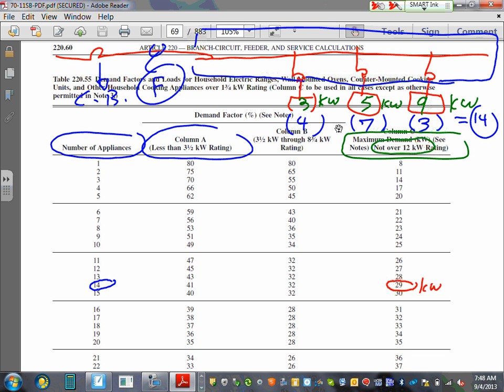You're going to say, okay, does column A apply to any one of them? Can you guys look at that? I have 3 kW. Is 3 kW under column A? Right? It says less than 3.5 kW. So all these ranges, column A applies to them. Can I have thumbs up? Yeah, we understand that, chat? Okay. Then you go to 5 kW. Is 5 kW under column B? Yep. So column B applies to them. How about the 9 kW? The 9 kW are not under any one of them, so I can't apply either A or B to them. So I have to apply C.